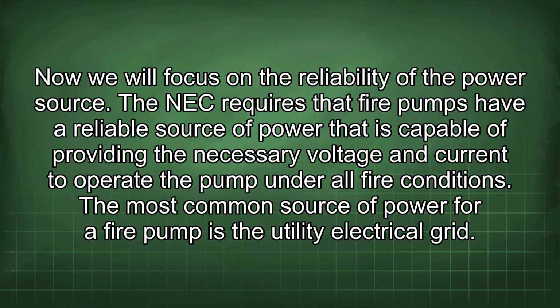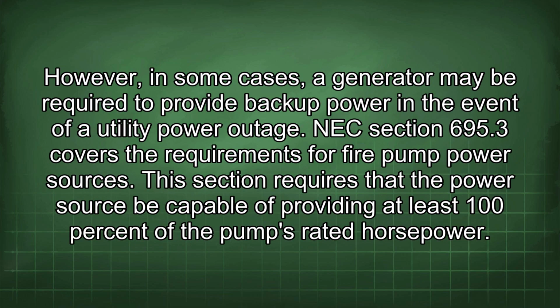Now we will focus on the reliability of the power source. The NEC requires that fire pumps have a reliable source of power that is capable of providing the necessary voltage and current to operate the pump under all fire conditions. The most common source of power for a fire pump is the utility electrical grid. However, in some cases, a generator may be required to provide backup power in the event of a utility power outage.